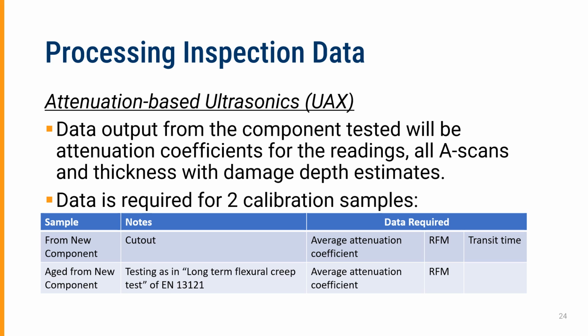For attenuation-based ultrasound, the data output from the component tested will be the attenuation coefficients from the equation that I showed earlier. All A scans and thickness with damage, and all of the A scans and thicknesses with the damage depth estimates will also be provided. We actually need data for 2 calibration samples, similar to what we just discussed for acousto-ultrasonics. We need a sample from the new component. What we need is the average attenuation coefficient, the RFM, and the transit time. And then aged from the new component. In other words, it could be a cutout after a period of time.